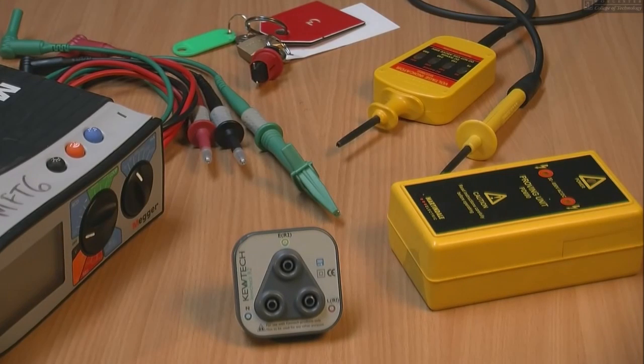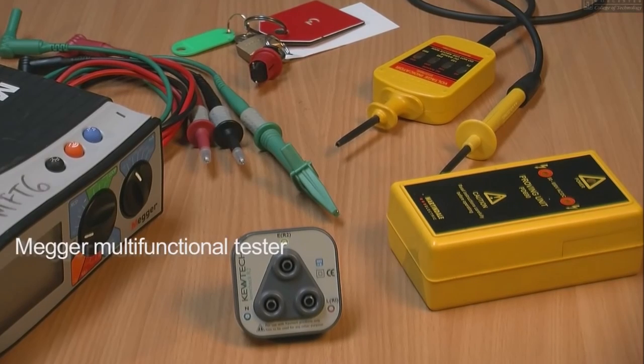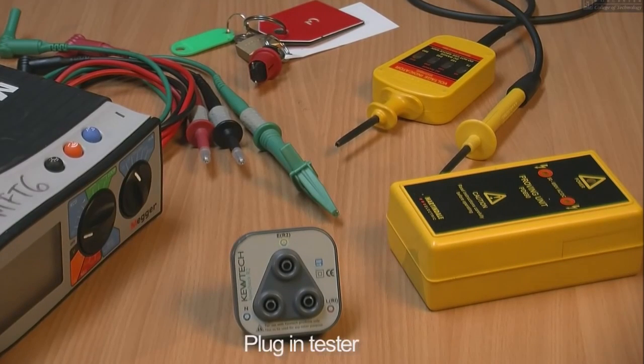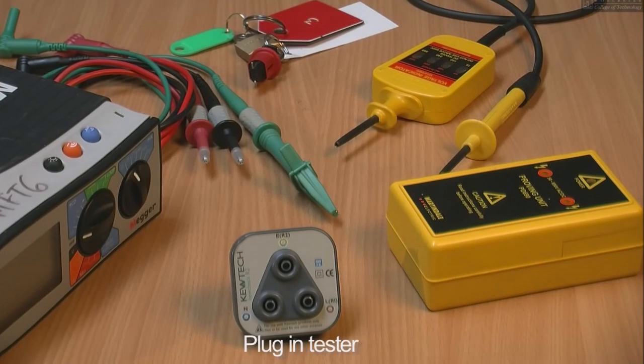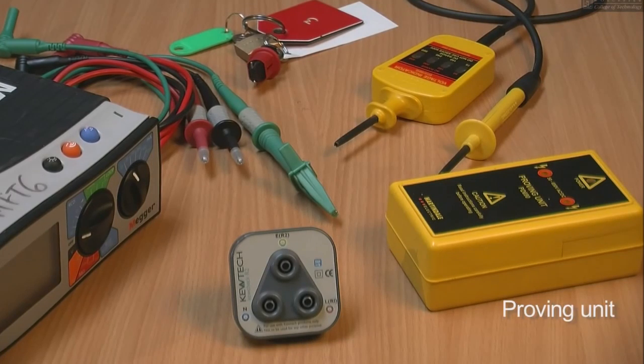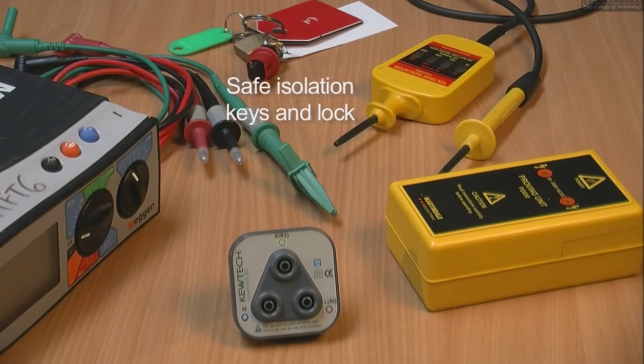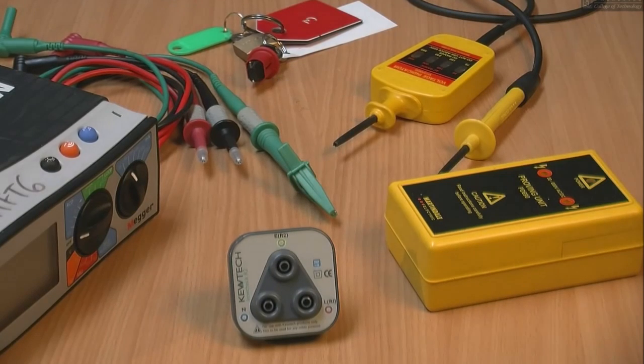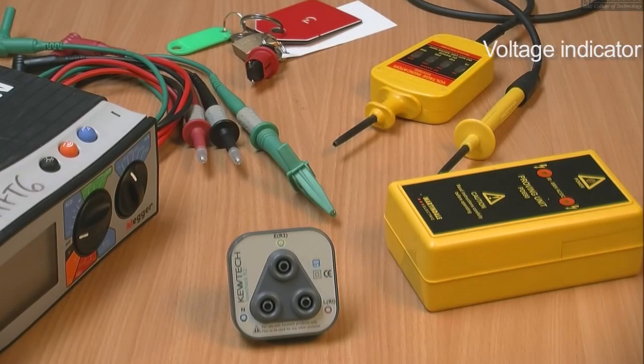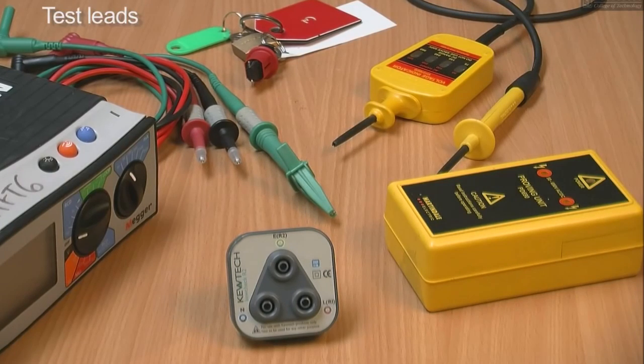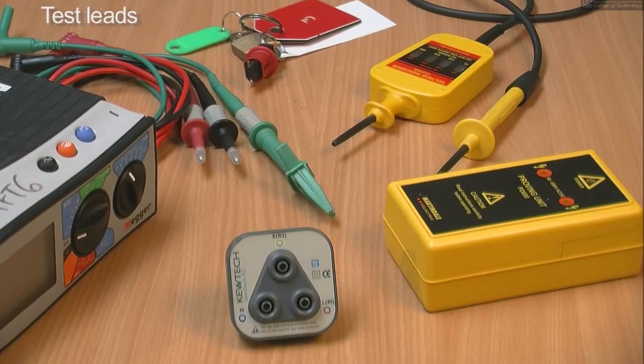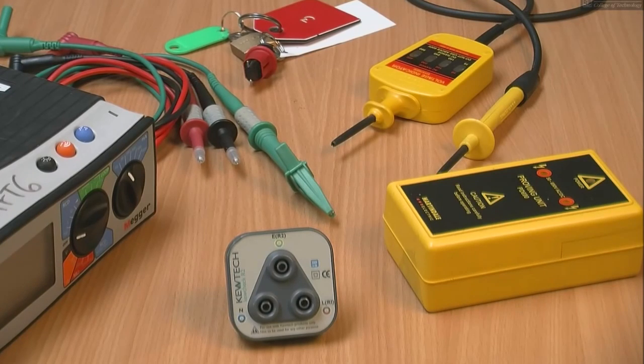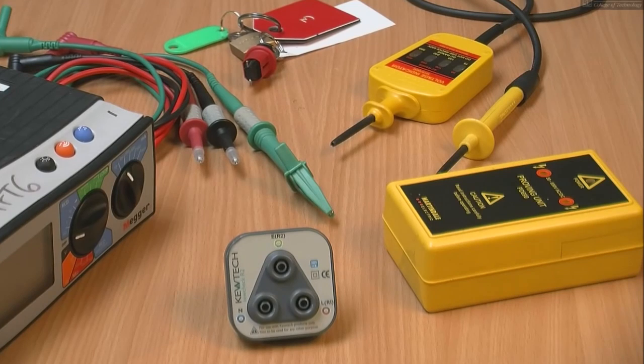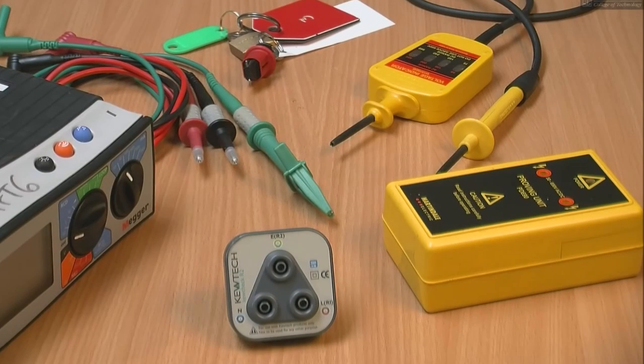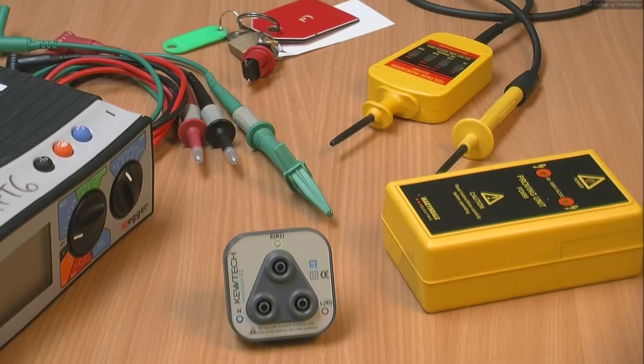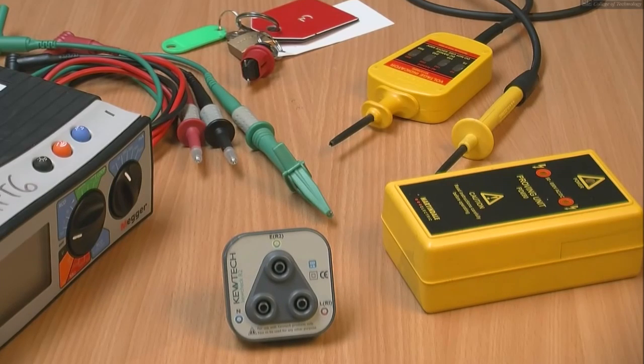We have a Megger multifunctional tester. We have a plug-in tester. We have a proving unit. We have a set of safe isolation keys and locks. We have a voltage indicator and a set of test leads complying to GS38, meaning that they have no more than 2 mil showing at the tips. They are fused, they have finger guards, and they have insulation and are robust enough to perform the live testing.